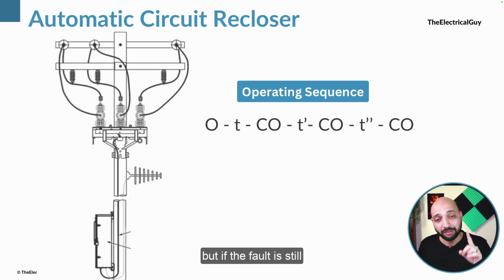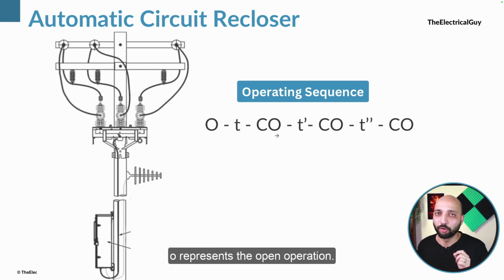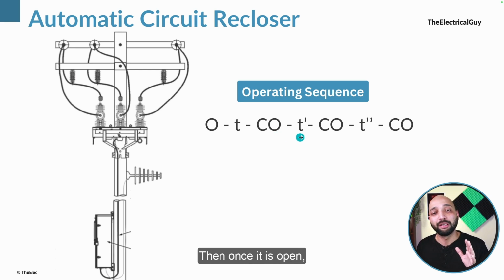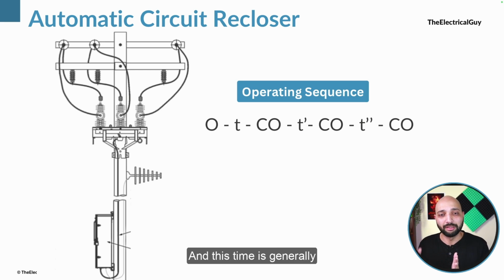But if the fault is still there in the system, it will immediately open. So C represents the close operation, O represents the open operation. Then once it is open, this time it will again wait, but for a little longer. This time is generally 2 seconds. After 2 seconds, it will close again automatically.